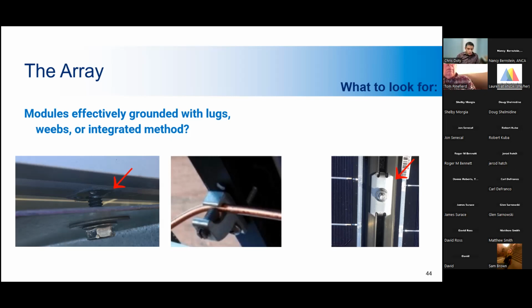So if you think about a roof mount installation, imagine a mason going on top of the roof to fix the chimney, and he accidentally touches the frame of a solar PV module. He could receive a shock of up to 600 volts DC or more, likely killing him. So grounding is one of the most important things in electrical installations because it's a safety issue, and if it's not done properly, it can cause serious injury or death. So that's super important. And also, a lot of the newer installations use integrated bonding.